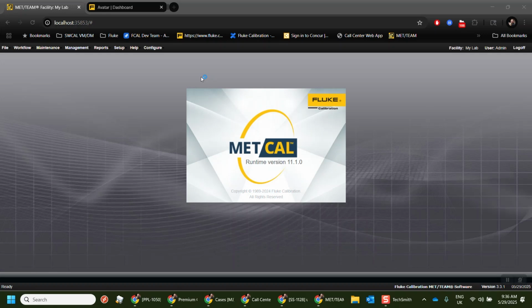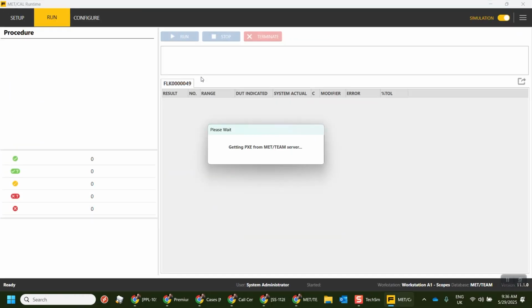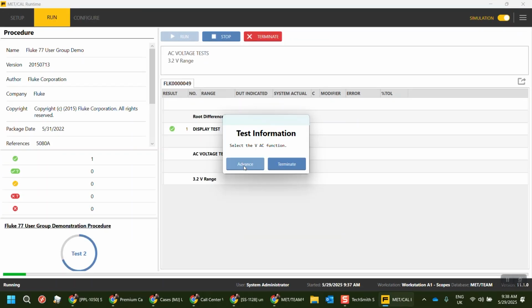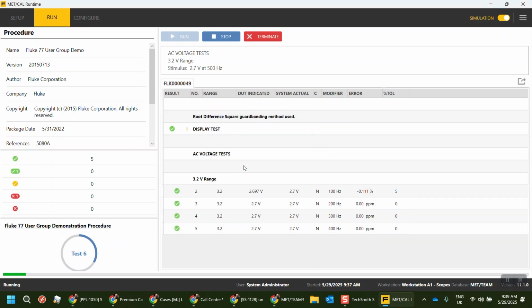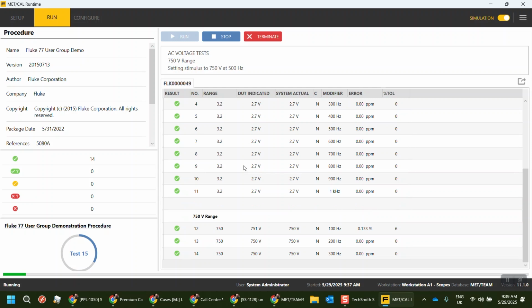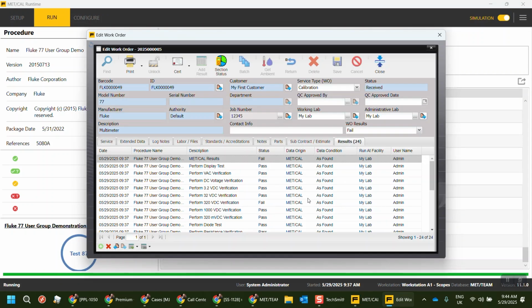Fluke Calibration sells the products to third-party laboratories, to primary laboratories also. We use all the span of Fluke calibration, like temperature, pressure, electrical, and also other kinds like radiation. We use MET, a software solution made by Fluke, and I use MET to create the procedures to do the calibrations automatized. When you obtain some knowledge and practice, you can do very interesting things to reduce the calibration time and to give services with good repeatability and reproducibility.